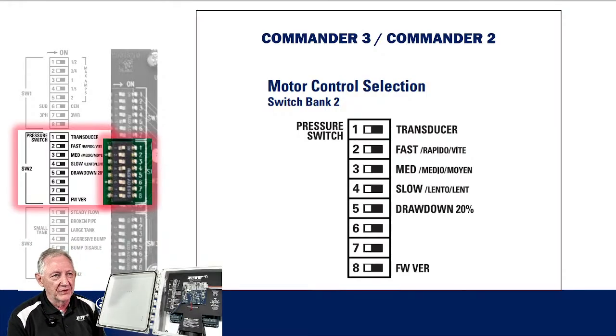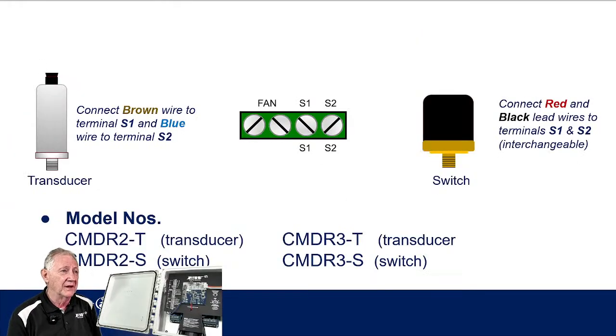But those have to do with response time. The instruction manual really relates to when we would want to use those. The drawdown has to do with the percentage below whatever pressure set point we're going to have, all right? And you've got a choice. The factory defaults at 5 psi or 5%, but you can go up to 20% with that drawdown. Again, that's how many PSI you want the pressure below the set point before this drive kicks on and runs everything back up to pressure again, right? How far do you want that to drop below set point?